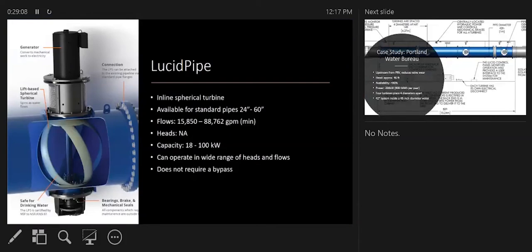Lucid Pipe is a new turbine design recently on the market, designed specifically for in-pipe applications. It's designed not to remove all of the head in the water, so you get positive discharge pressures. It's available for standard pipes from 24 to 60 inches, in 3 different sizes. So these are pretty big pipelines, like supply lines, and you need a pretty big flow for these. This technology looks really promising, but it wouldn't be applied where you need very fine tuning of pressure and pressure management.